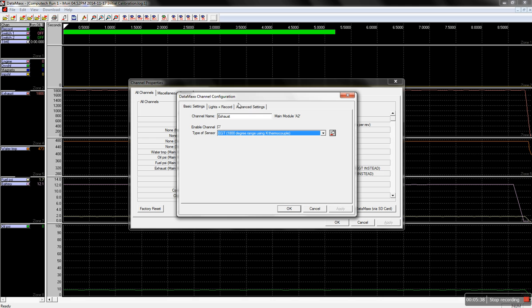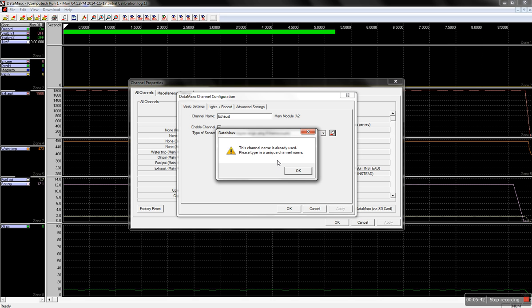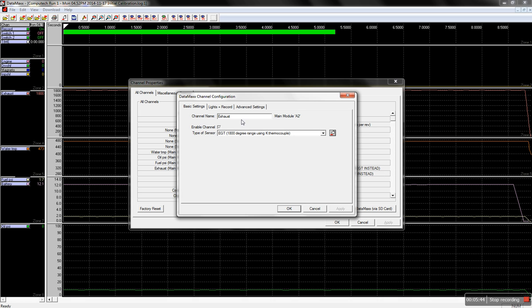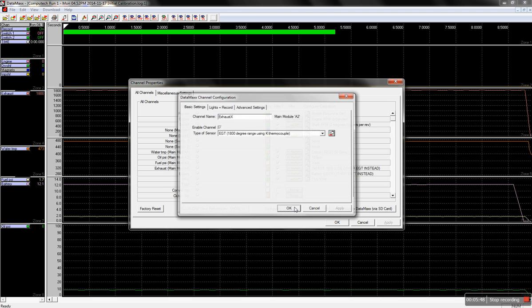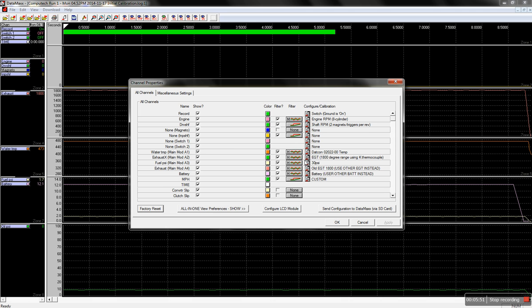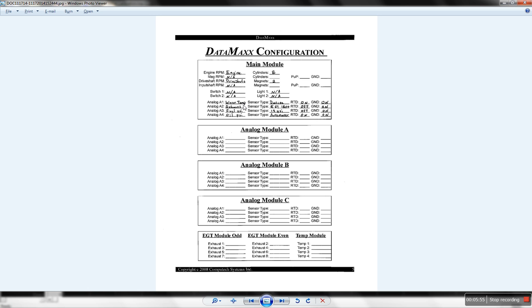Now what's going to happen is, because we already have a channel name of exhaust, when we hit OK, it's going to say this channel name is already in use. So what we're going to do is temporarily call this exhaust X. Hit OK. Now we've got exhaust, and it is the correct type of sensor that does in fact match up with our configuration sheet. So next sensor is A3.